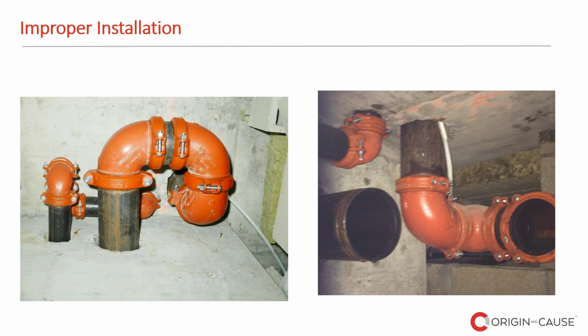Again, improper installation can also mean some of the mechanical fittings not being properly tightened and they just become loose. This is a 6-inch pipe, and you can imagine the amount of water that came out of that. It was so much water and so much pressure that it actually destroyed a cinder block wall in that building. And this was right in the lobby when that cinder block wall exploded, as it was described by the property manager. Everyone thought it was something else. So luckily nobody got hurt, but significantly damaged because of improper installation.